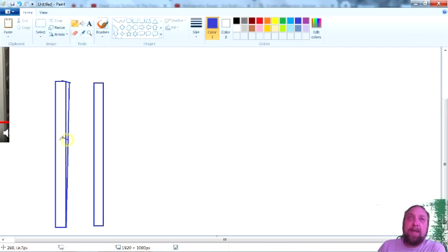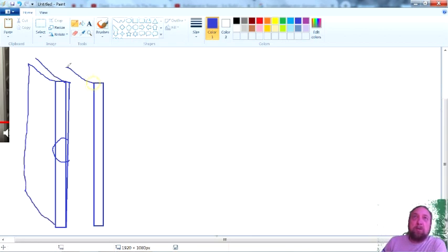You put one hand on this side and the other on the other side. Let's say this is the door going all the way out, and this is the opening of the cabinet, the inside of the freezer. You would put one hand on either side of the door and slowly pull out, right from the middle about where the track is, so we don't cause the top or the bottom to lean back and lose our alignment. So we slowly pull it out without any force so we don't mess up the adjustment, and then we tighten those screws down to retain its shape, and now open and close the door and see if it seals.